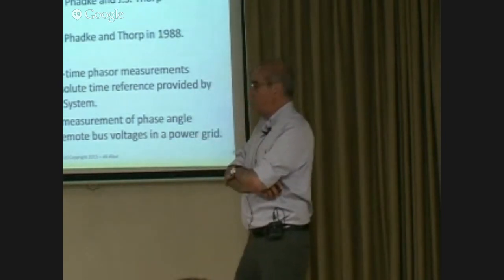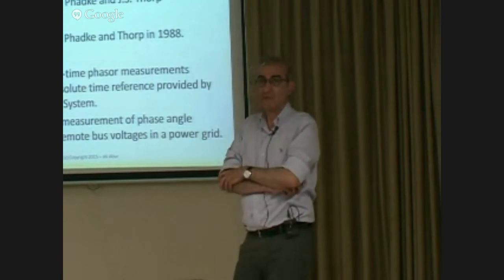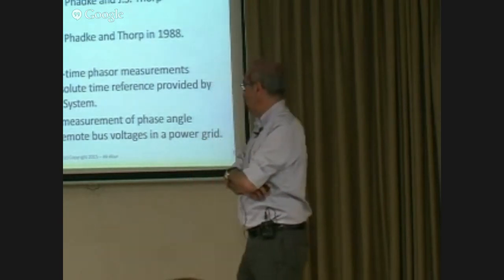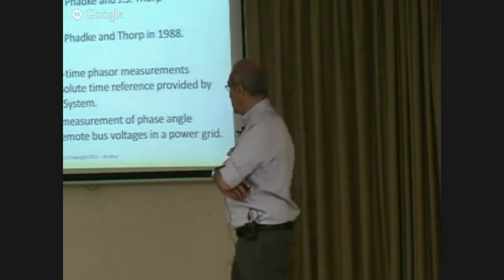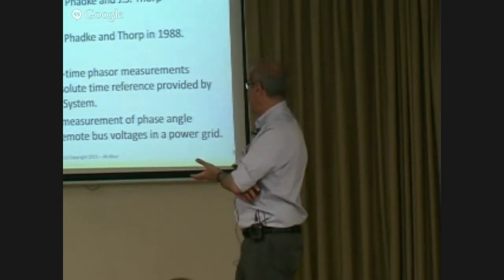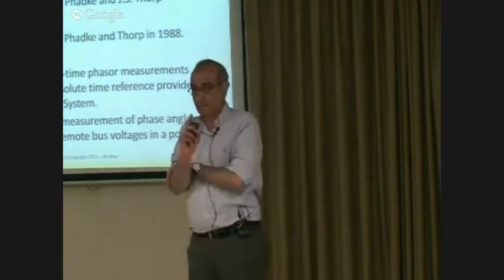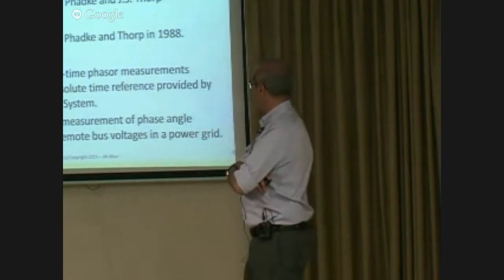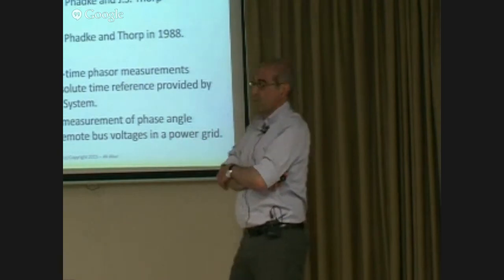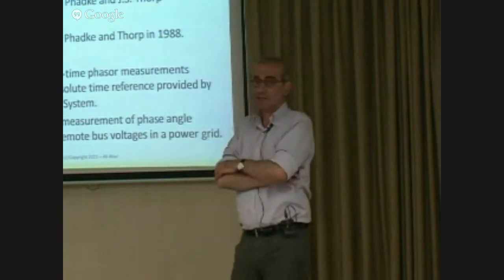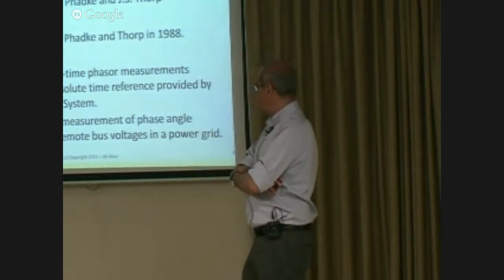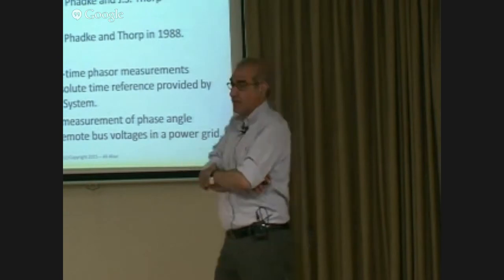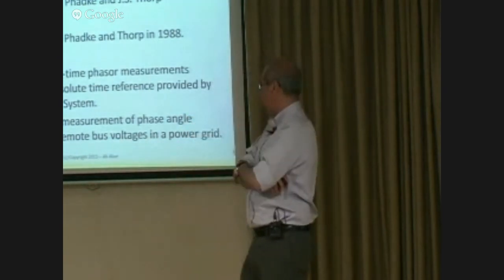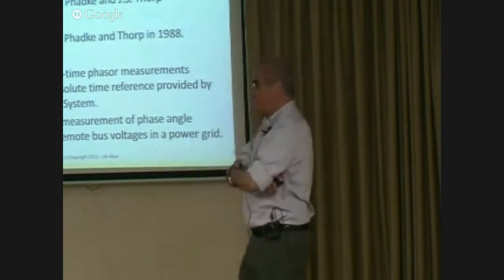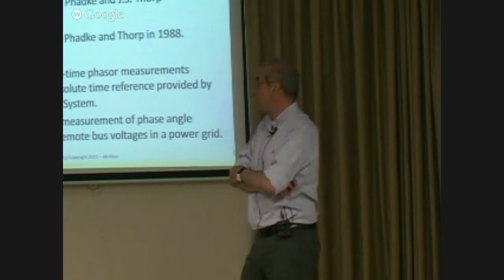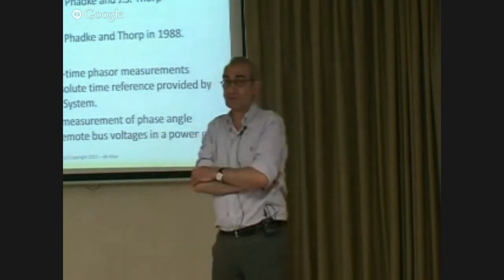Since then, we've seen several manufacturers producing it, and people deploying them in power systems. So what is it? It's a real-time Phasor measurement, using synchronization through GPS so that you can get phasors measured in a synchronized fashion at remote locations in a given system. For us, the main advantage is that we can get phase angle differences between two remote points in the system, which we didn't have earlier. Direct measurement of this didn't exist earlier.